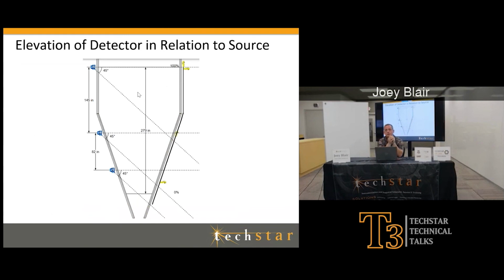and you get your paperwork back showing you the orientation, you'll see that you've got 45-degree angles. Okay, you can see where each one of these passes and they kind of intersect on the right-hand side, so that I'm fully painting this vessel with radiation in this picture. Also see that it looks like I have a high level switch on this particular one and a low level switch. So I have both. And this installation looks fine. We'll measure all the way down. You can see where my radiation beam on the bottom passes. I'm going to measure all the way down to that point. As long as everything is installed in the right location and it's where it's supposed to be, I should have absolutely no problem with this.